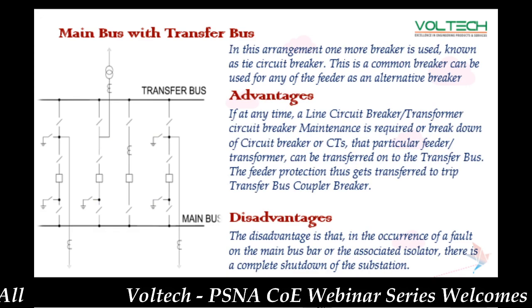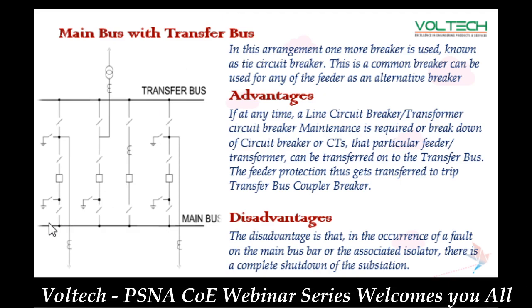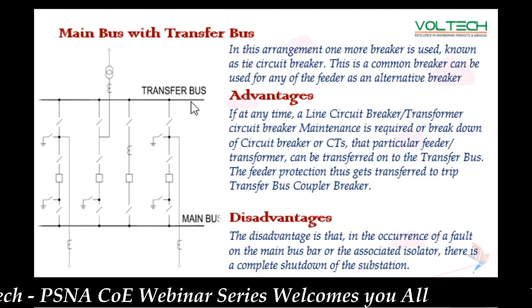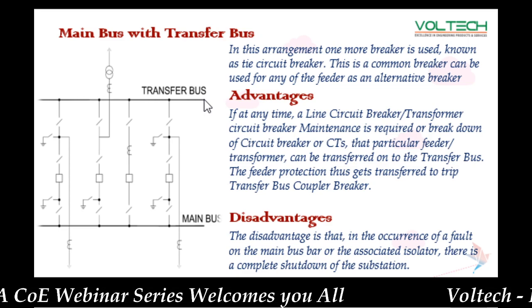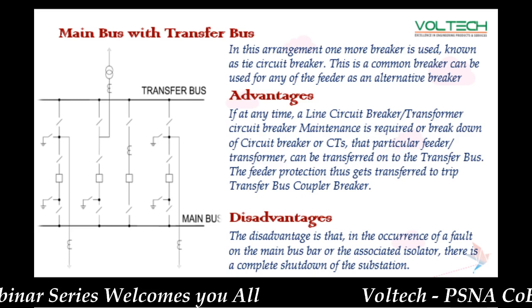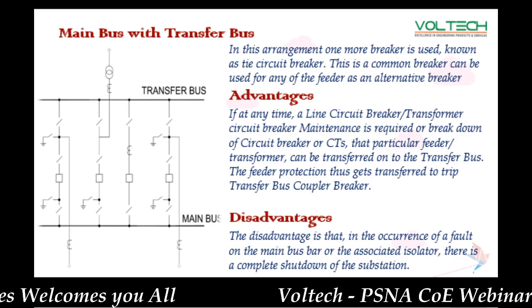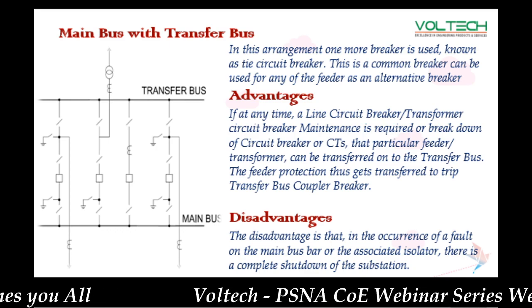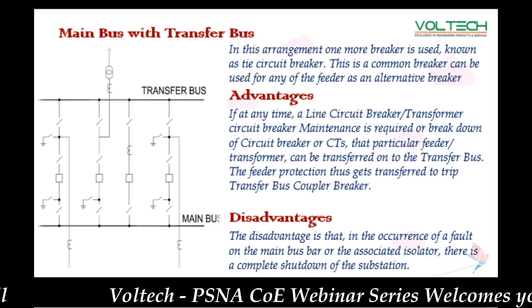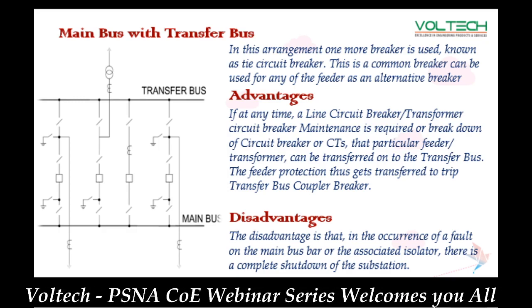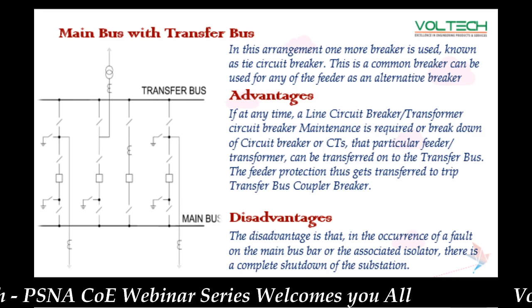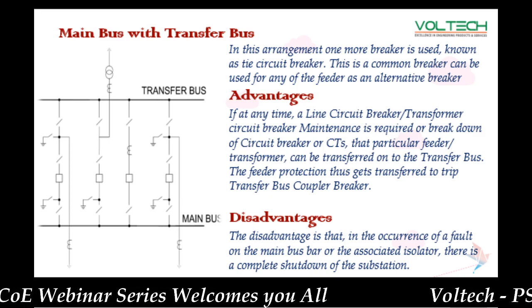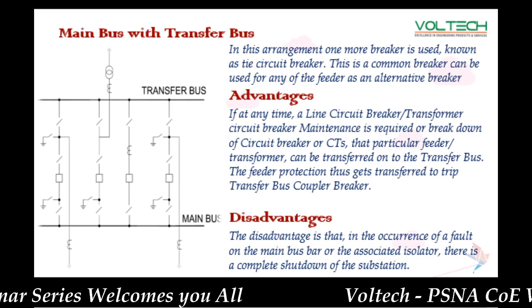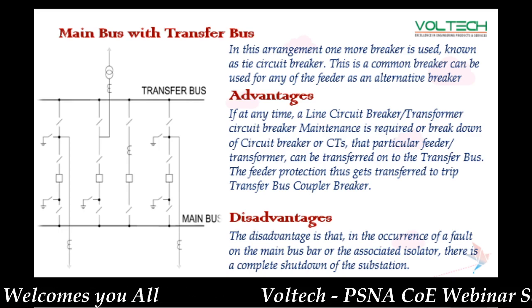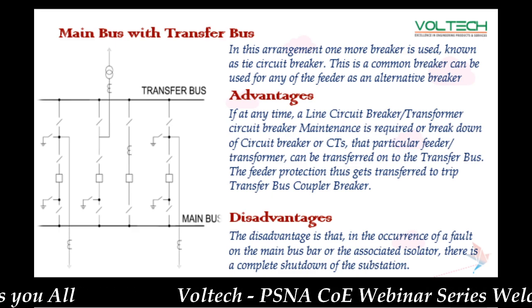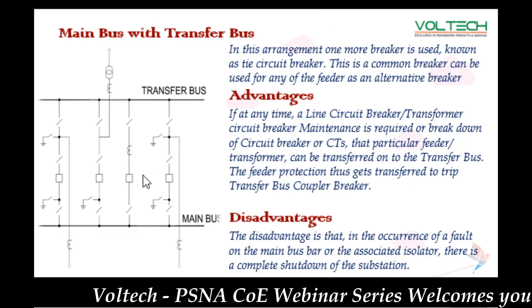Okay, this is main bus with transfer bus. That means one single bus and with the transfer bus. We call it main bus with the transfer bus, which means we are using one as a main bus bar and one as a transfer bus. The transfer bus is nothing but the same type of bus bar as the main bus, but we use it only during the maintenance period. Without shutting down the substation or any other equipment, we can transfer the load from our main bus to the transfer bus. Then we can carry out the maintenance operation.